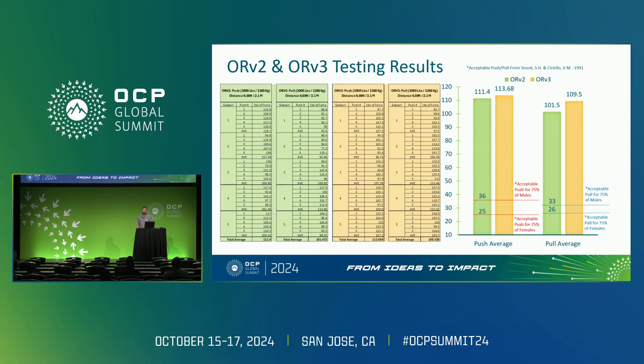These numbers are particularly significant when we consider ergonomic standards. According to Snook and Ciriello, the acceptable push and pull forces for 75% of the population are much lower. For males, these limits are 36 pounds for a push and 33 pounds for a pull. For females, the limits are even lower at 25 pounds for a push and 26 pounds for a pull. The forces required to move both the ORv2 and ORv3 racks loaded to 3,000 pounds are well above what's considered ergonomically safe for most people.